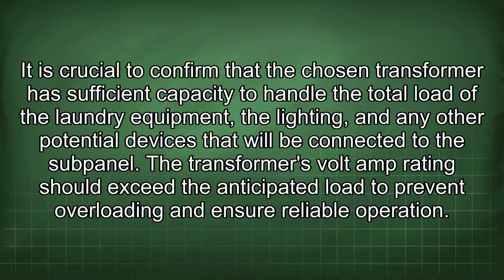It is crucial to confirm that the chosen transformer has sufficient capacity to handle the total load of the laundry equipment, the lighting, and any other potential devices that will be connected to the subpanel. The transformer's volt-amp rating should exceed the anticipated load to prevent overloading and ensure reliable operation.